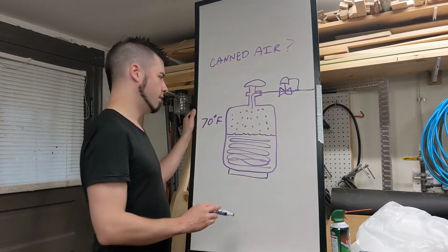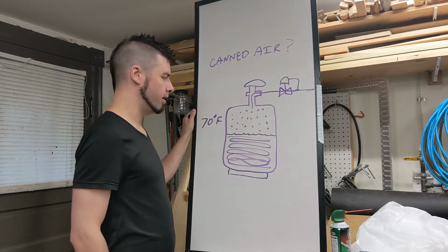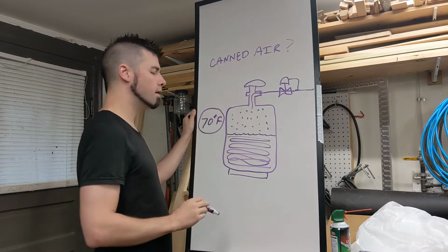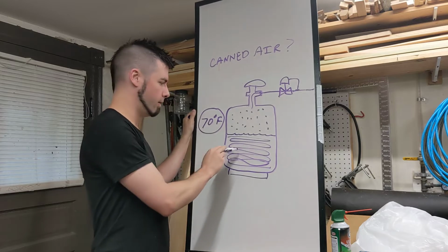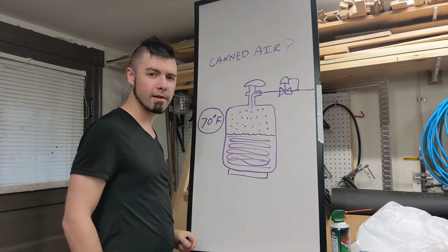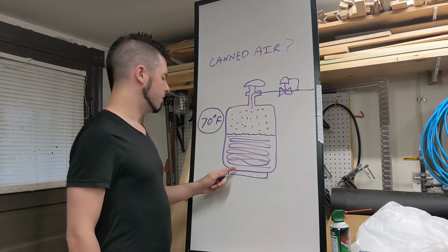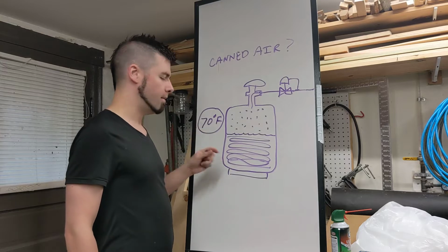And the gas pressure inside the tank above the liquid is completely dependent on this pressure or temperature when liquid is present in the tank. So if we have liquid propane, even if it's a single milliliter of liquid in your propane tank, that pressure in that tank is completely dependent upon the temperature of that liquid.